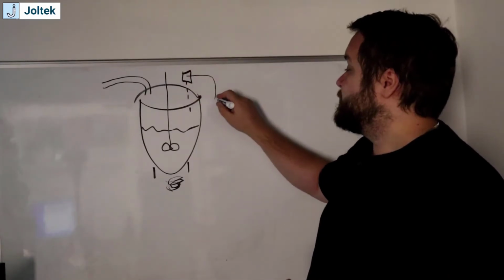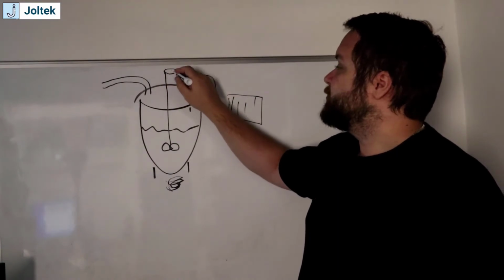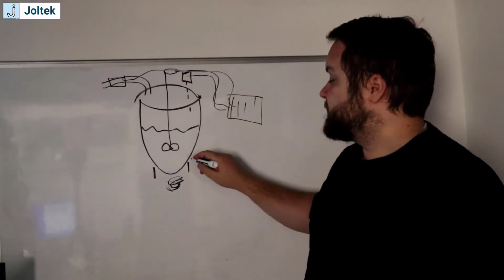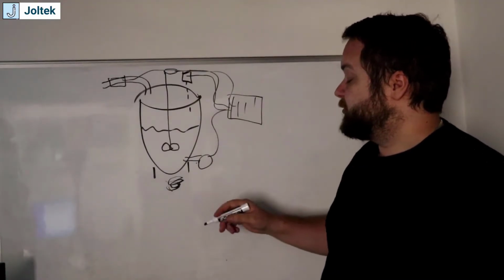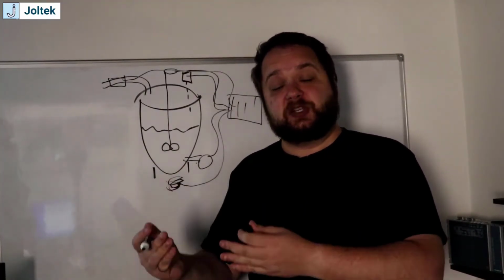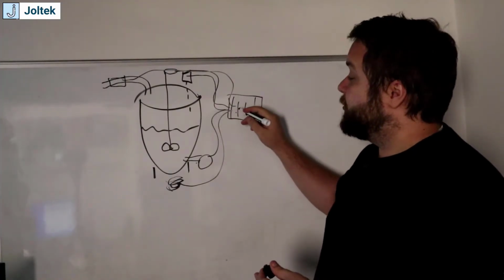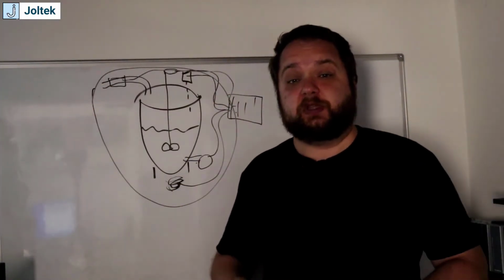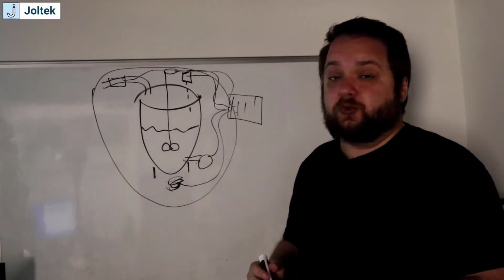So you have a connection from the sensor going back to an IO rack with PLCs. You have the motor that's controlling the agitator. You have some kind of flow meter on the pipe that's also going to tie into this. There's maybe a discharge motor going to a different tank that's also going to go into your PLC. The heater, of course, is controlled by the PLC. So the control loop in industrial automation systems is basically what you're going to be programming as the state logic inside of your PLC to get your system to the desired outcome, which in this case could be mixing different ingredients, heating up to a specific temperature, and then sending that off to a different batch.